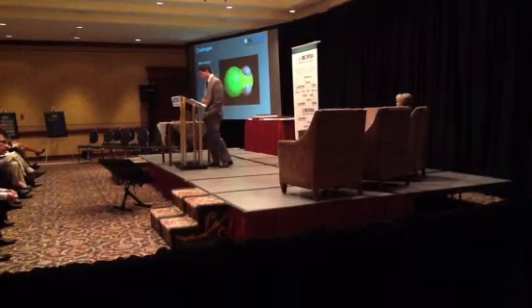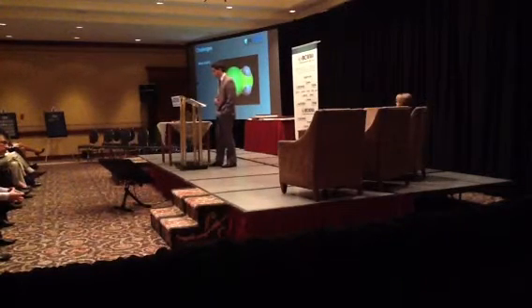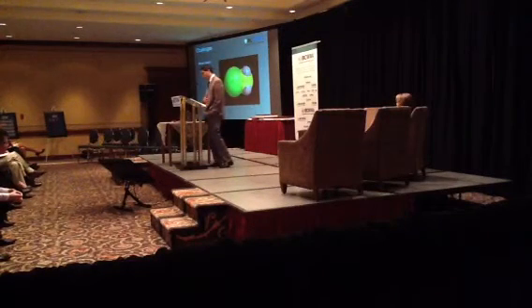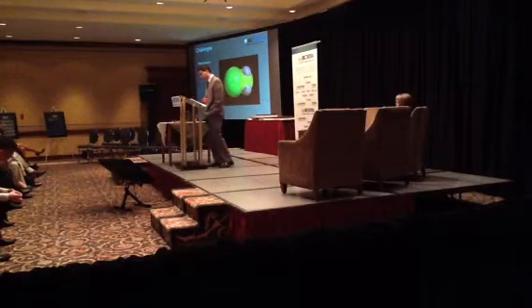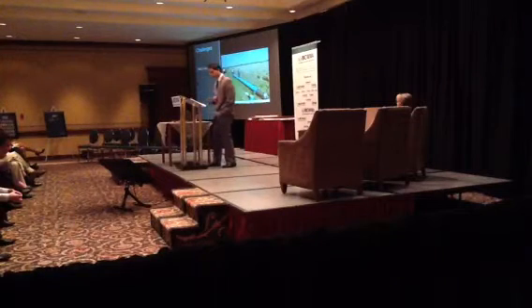We will review a few different challenges that we encountered over the next few slides, water quality being the first. Water being supplied to ACE can be up to 3 weeks old. It can age an additional 50 days in the ACE system and have a total age of 71 days. Lab testing showed that we needed to boost chloramine levels, no surprise, but it may only be required during summer months, and we only needed to boost at the water transfer station.